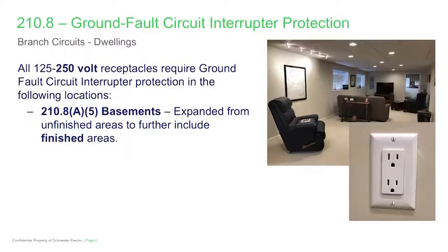As we look at 210.8(A) for residential dwellings, the hazard is the same whether it's a 125-volt receptacle or a 250-volt receptacle. The code panel recognized the areas where the hazard is the same and why there doesn't necessarily need to be a limitation on voltage. Basements have traditionally focused on unfinished areas, and now include finished basements — the same hazard exists where the potential for moisture or water on the floor creates a damp or wet location. This expansion will make it easier for code enforcement and the installer. Now, if it's a 125 or 250-volt receptacle in a basement, period — it'll have GFCI protection.